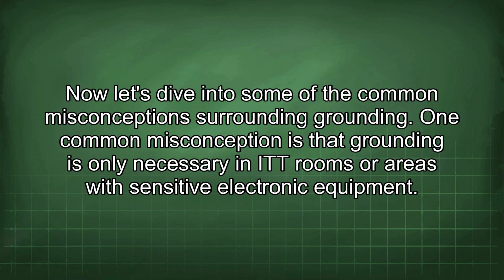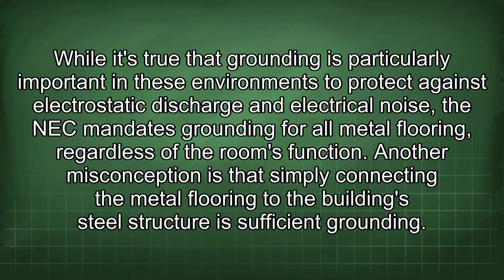Now let's dive into some of the common misconceptions surrounding grounding. One common misconception is that grounding is only necessary in IT rooms or areas with sensitive electronic equipment. While it's true that grounding is particularly important in these environments to protect against electrostatic discharge and electrical noise, the NEC mandates grounding for all metal flooring, regardless of the room's function.